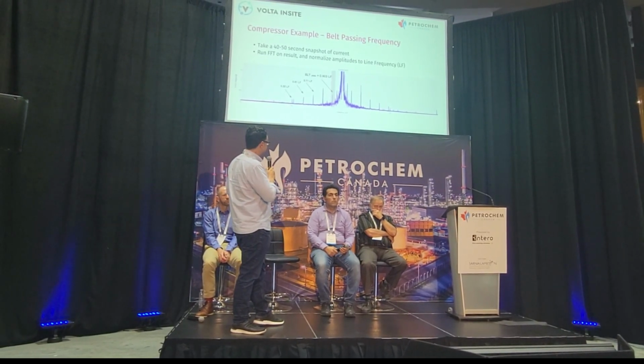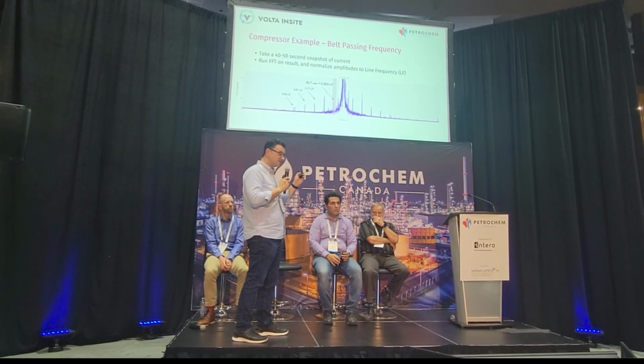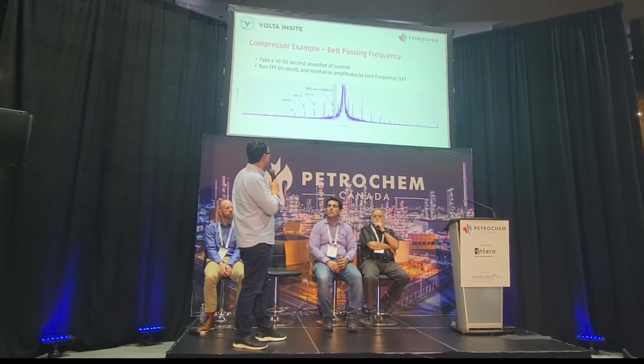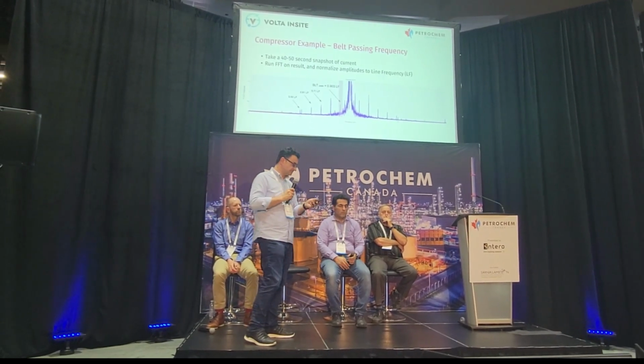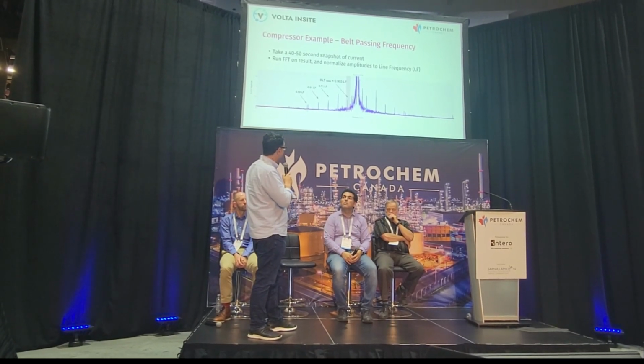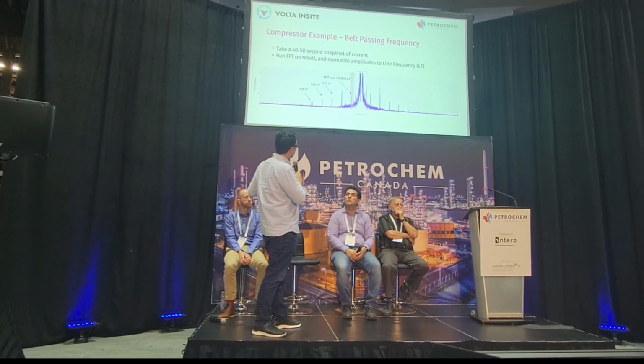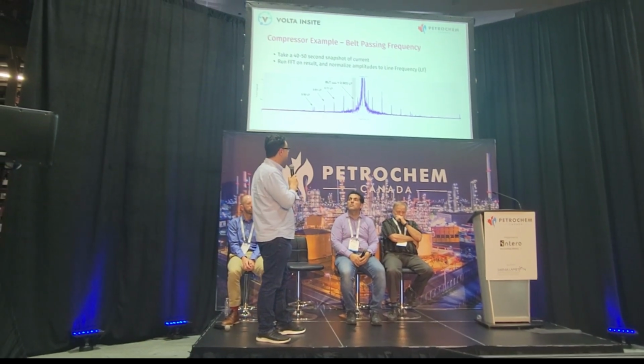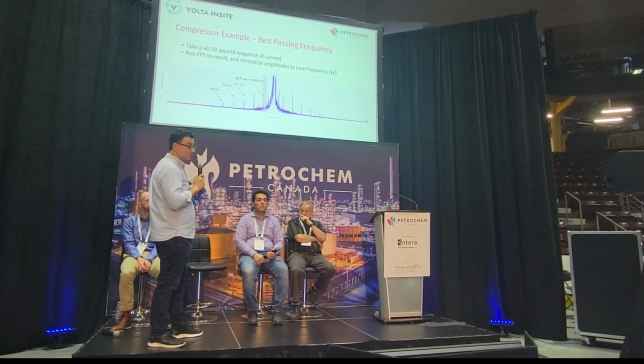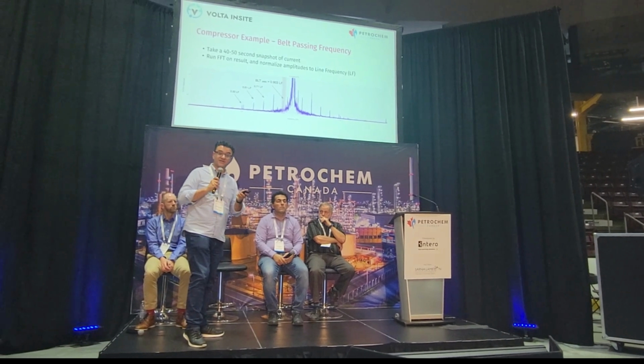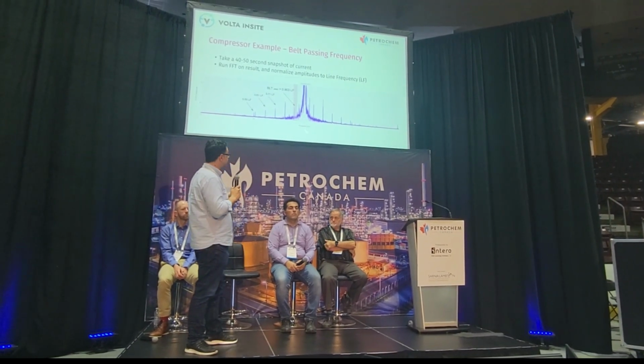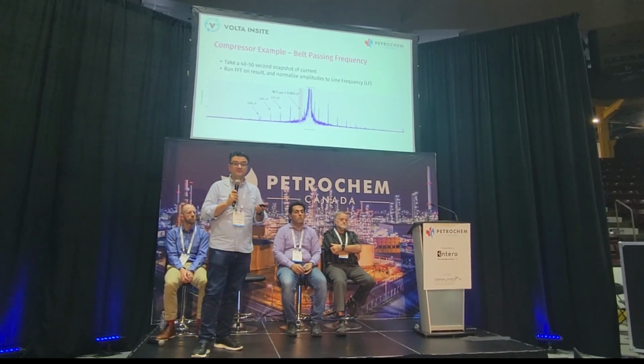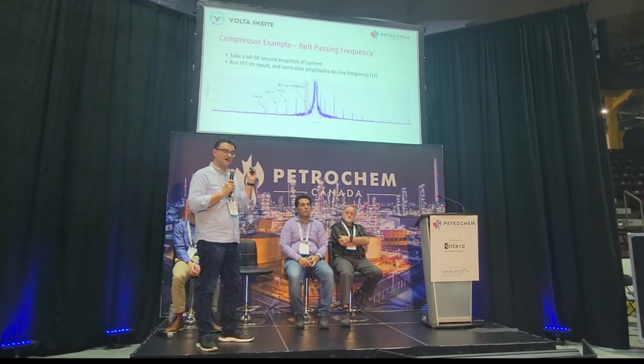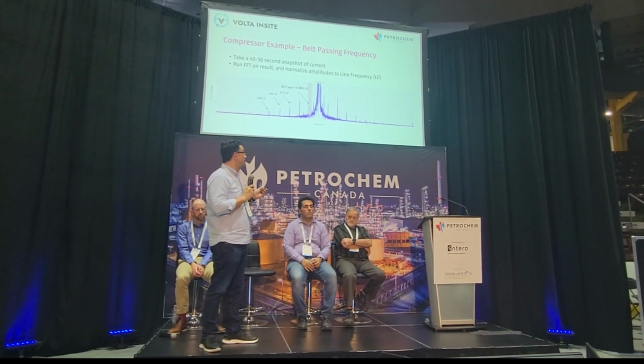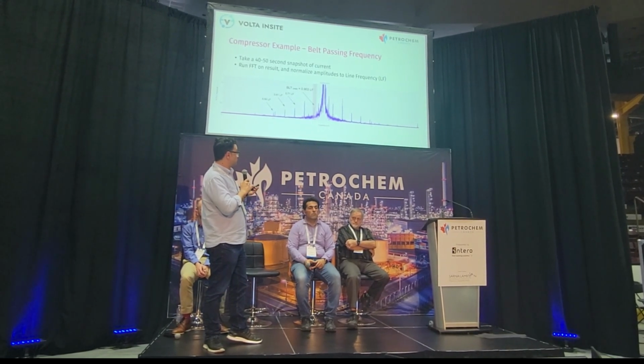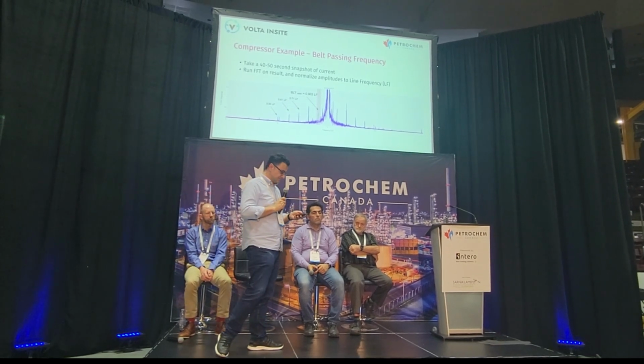So this is the concept of electrical signature analysis, and all the harmonics, if you have a gearbox and so forth, I'll get into some more examples, are associated with a particular current signature. One additional note is that we normalize the harmonic spectrum with regards to line frequency. That's why it's 1. Traditional aspects of electrical signature analysis either use 50 hertz or 60 hertz. This is useful in the application of VFDs. When VFDs are running at multiple speeds, now you can have a basis to trend all the harmonics based on the actual gearing associated with that system.